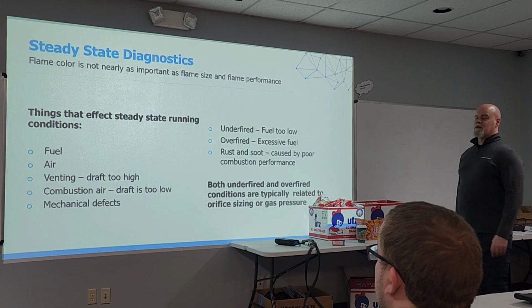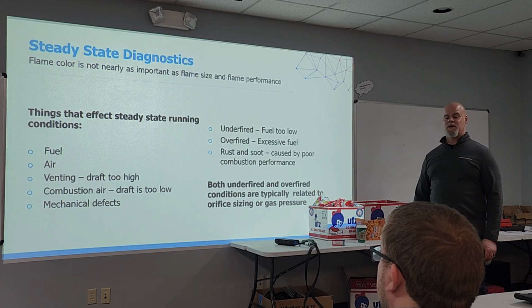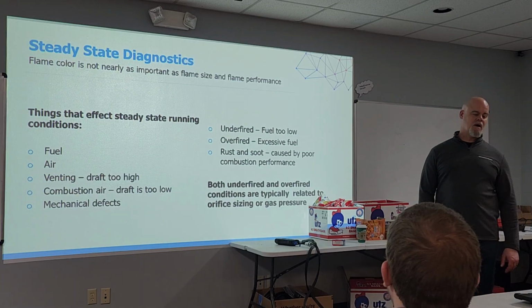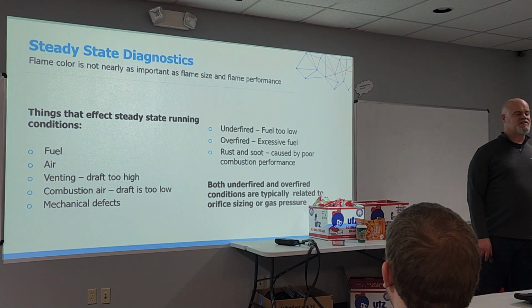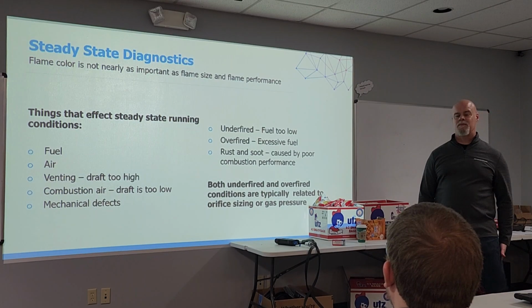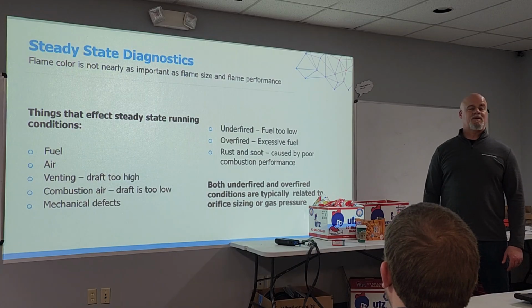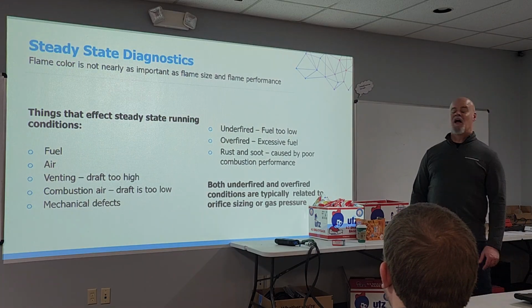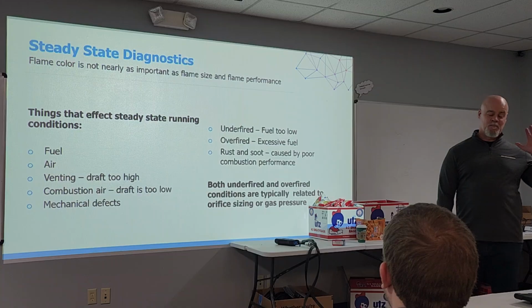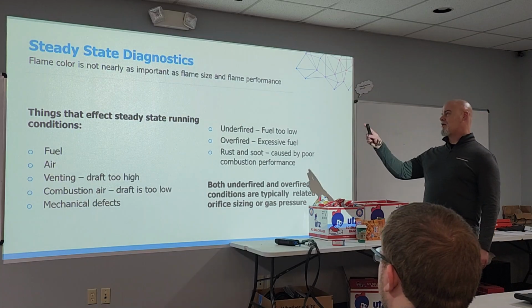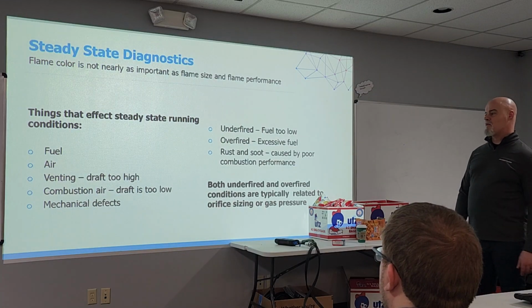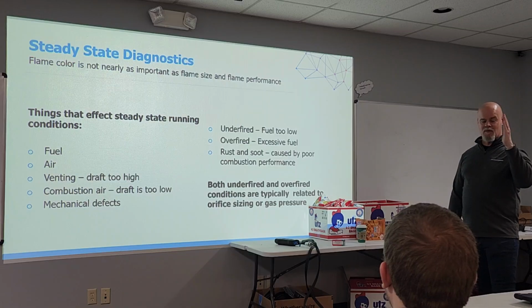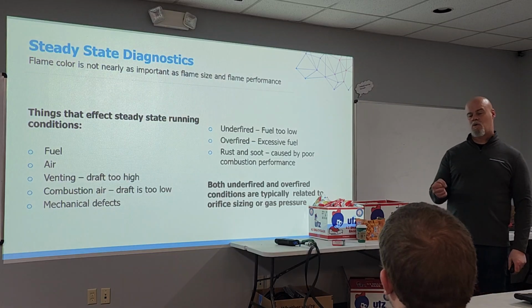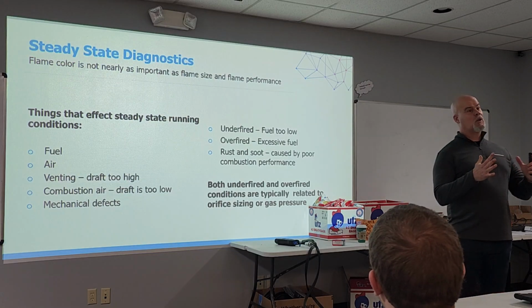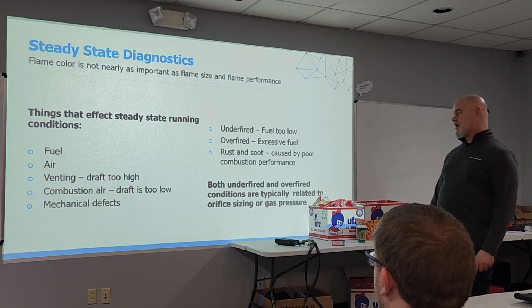Steady state. I don't care about your flame color. Don't tell me you have a nice pretty blue flame like you'd see on a gas company emblem. That doesn't work for me. I have seen 3,500 to 4,600 ppm on a nice blue flame that everybody thought looked pristine. It can look pristine, but the CO is still through the roof. I care about flame size and flame performance. I don't want flame erratic behavior. I want a controlled pattern. I don't want an elongated flame, which I'll get to.